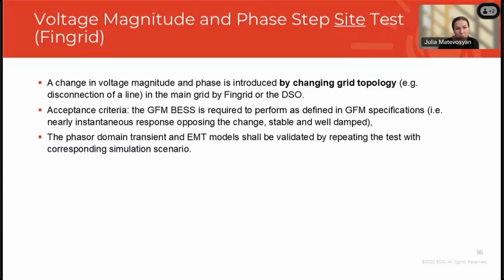Interesting thing I wanted to point out is that FinGrid actually is the only one that specifies site tests for all the documents that I've reviewed so far. And so basically for the voltage step change, they will have a test where they will change topology of the grid. And so that will result in voltage magnitude change, but also voltage step, phase step. And acceptance criteria is that it's required to perform according to requirements. And they will also do phasor domain and EMT domain model validation based on those test results.